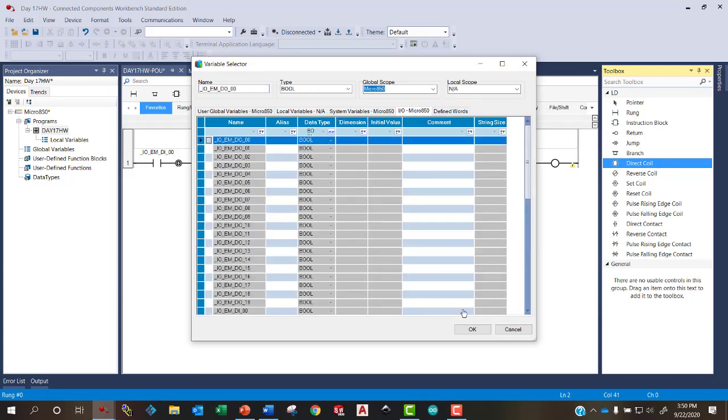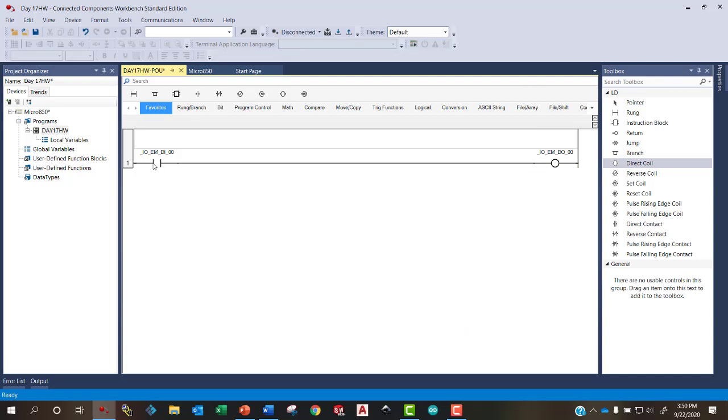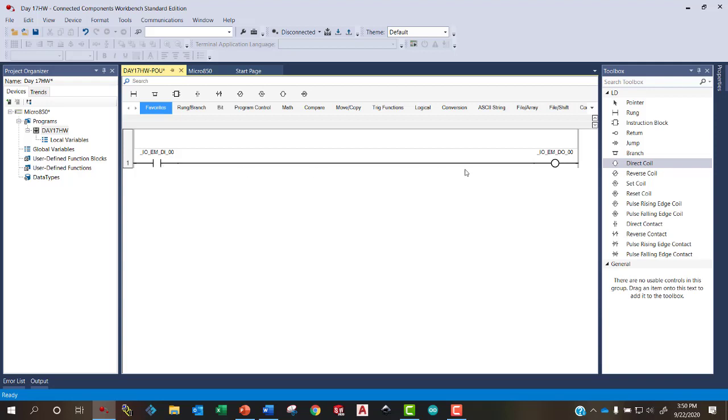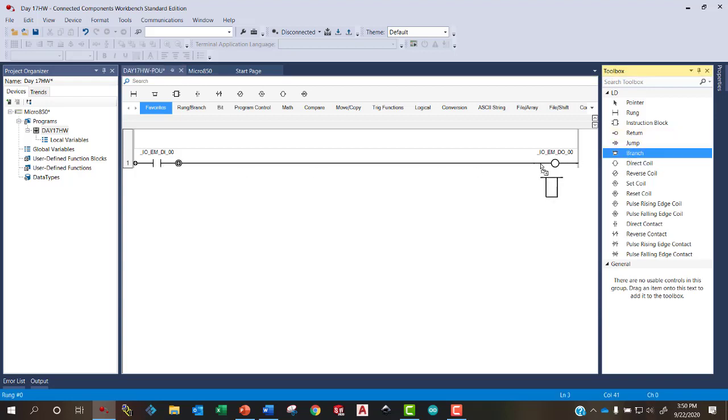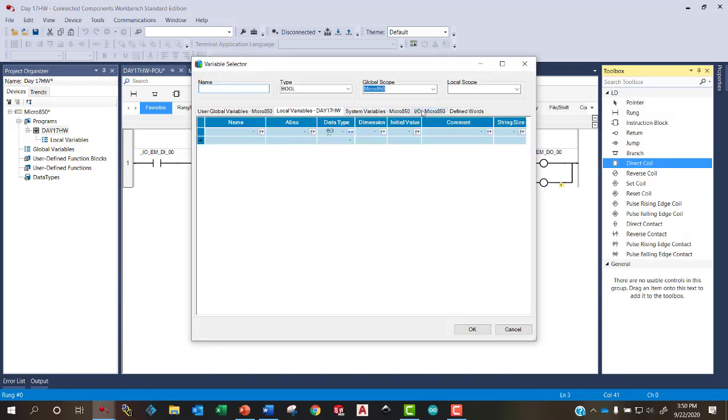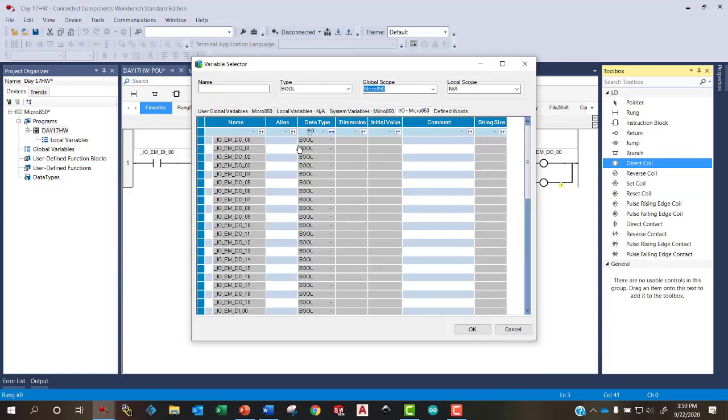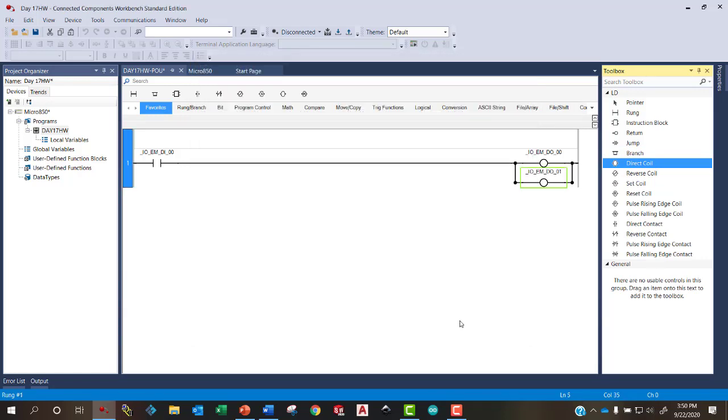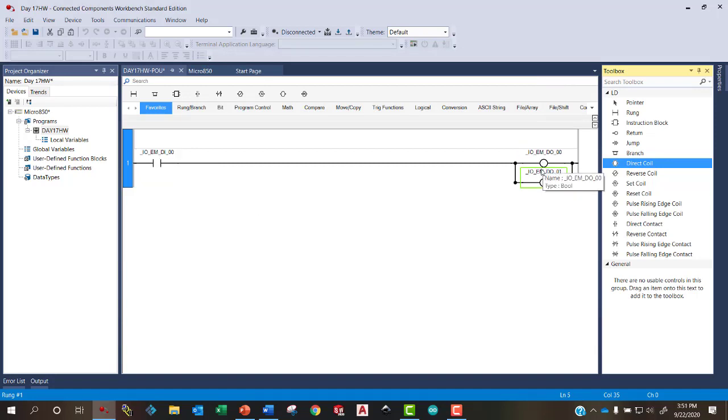Now I can grab a direct coil and drag it onto this rung. And now let's connect that to Digital Output 00 on my PLC. Now when this contact closes, this output will be energized. But I want it to energize two different outputs when this direct contact is connected. So let's grab a branch and put the branch right here. And so now it's also a parallel branch where I can drag another direct coil and place it here. And in the I.O. let's connect that to Digital Output 1. When this input 00 is pressed, both of these will now energize.